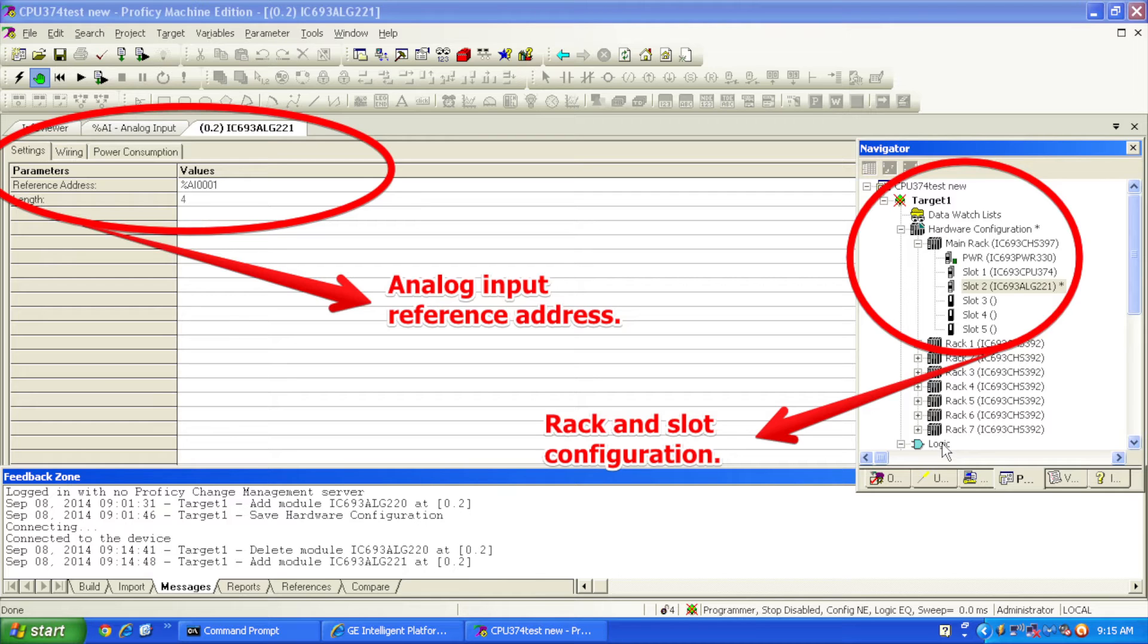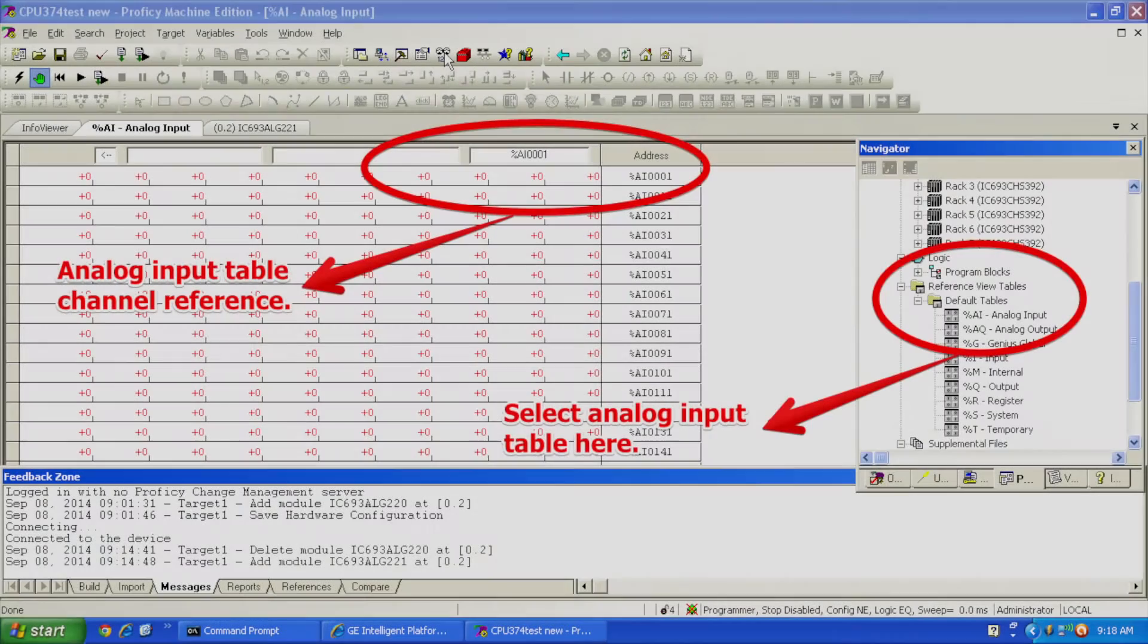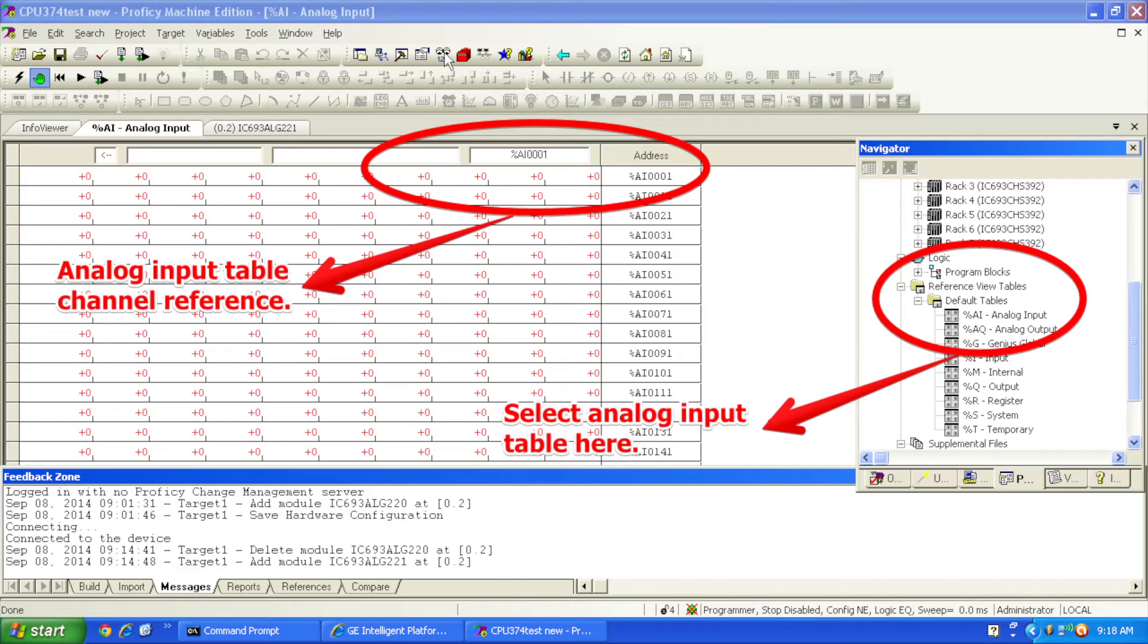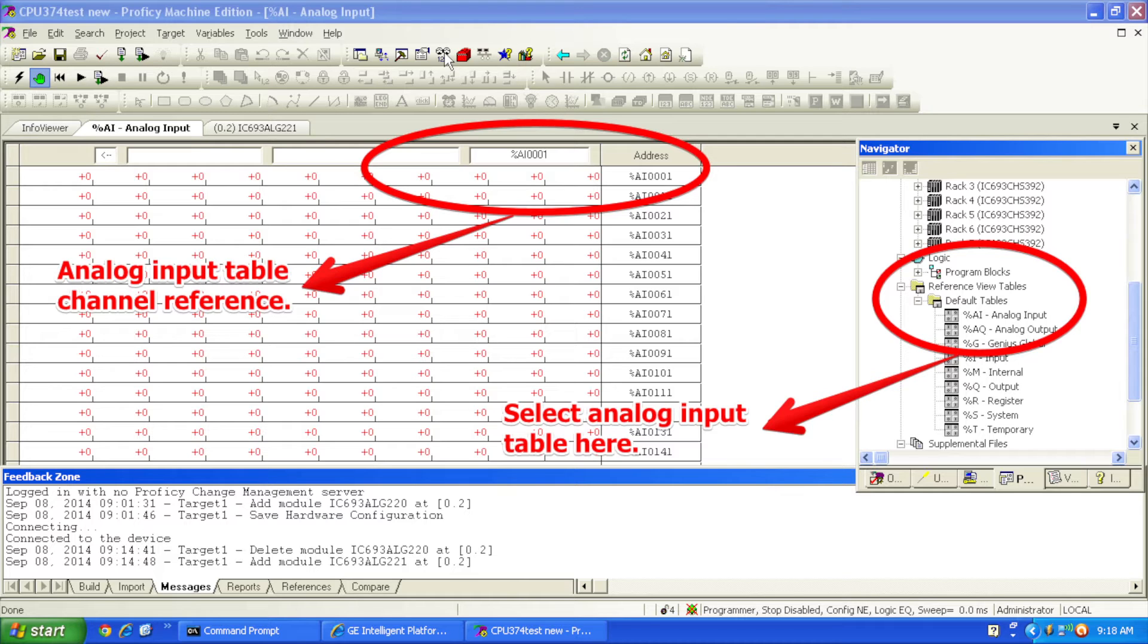That tells me where I'm going to be able to see the readings that the device is giving me. What I want to do now is go to my default tables underneath reference view tables and select the top selection, which is %AI or analog input table. You can double-click on that or right-click and open. Then you'll have your reference table so you can see the readings that the card is giving you.